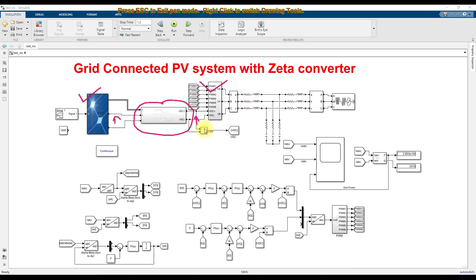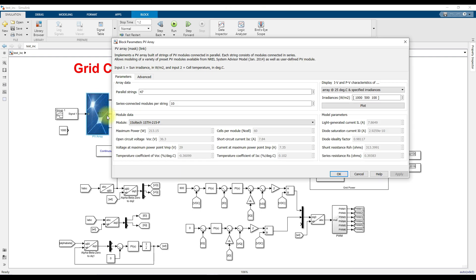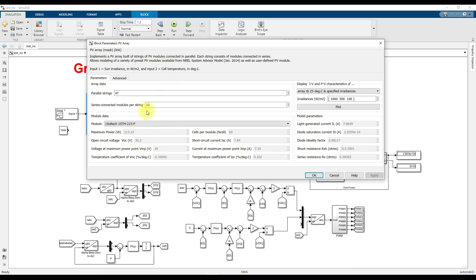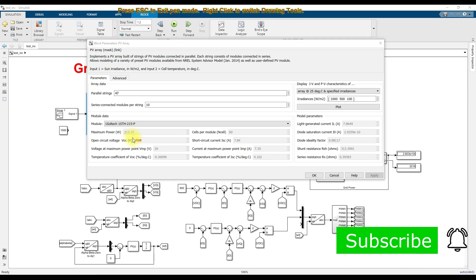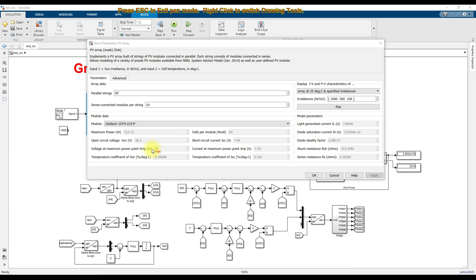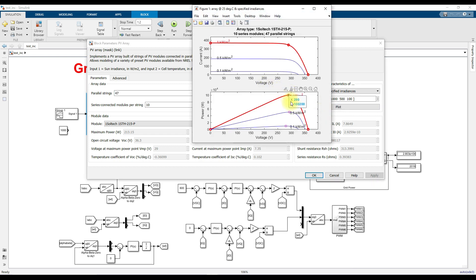Here you can see that we are having a PV array — a single string having 10 series modules, and in total 47 parallel strings. Each panel has a maximum power of 213.15 watts, voltage at maximum power point is 29 volts, and current at maximum power point is 7.35 amps. It can supply a maximum of 100.2 kilowatts. The voltage of the PV at standard test condition is 290 volts.